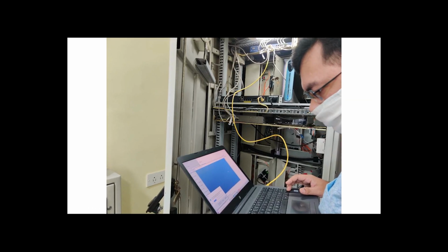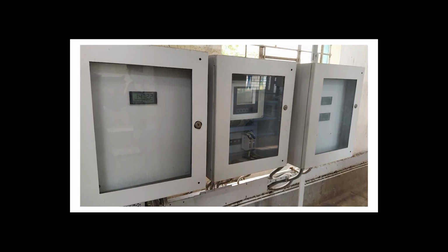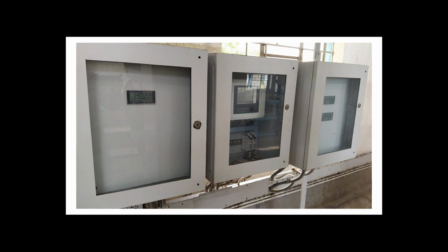It was through an automation process developed by our team with the joint effort of hydraulic engineers, software engineers and IT professionals. Selection of the mobile SIM was an important factor. A recon was done at all sites to assess the mobile connectivity and which mobile company gives service at different locations. Accordingly, the SIM was procured from one service provider for all instruments. As the data would be transferred through text message, the instruments procured were compatible with a 2G connection.